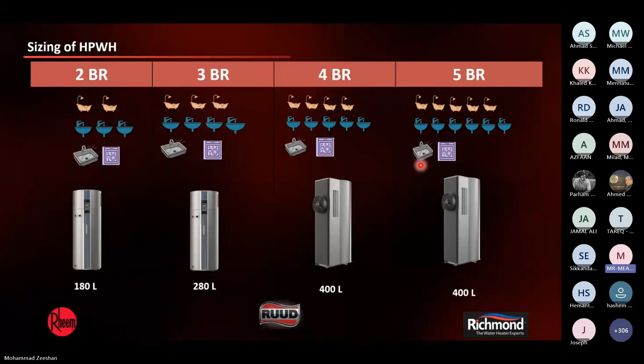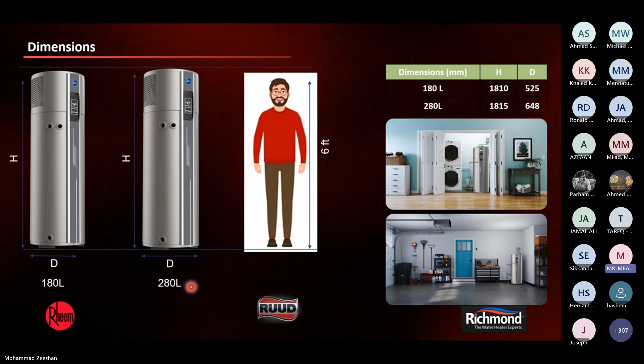In terms of the height of the system, it's important to understand this so you can plan your pump rooms. It's one thing to know about the product, and another to actually use it, so it's very important to imagine the height of the units. Picture a 6 feet tall person right next to the heat pumps to imagine their height. The width is about 525mm for 180 liters and 650mm for 280 liters. This is mostly for 50 hertz markets. For 60 hertz, like Saudi, it is slightly different, but you can use the same data for planning your pump rooms.